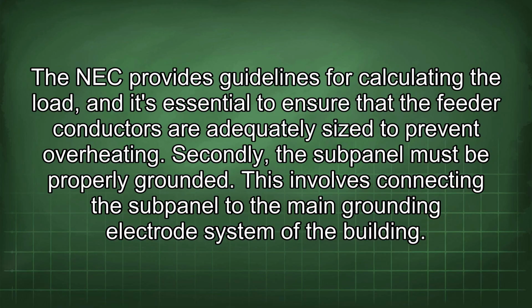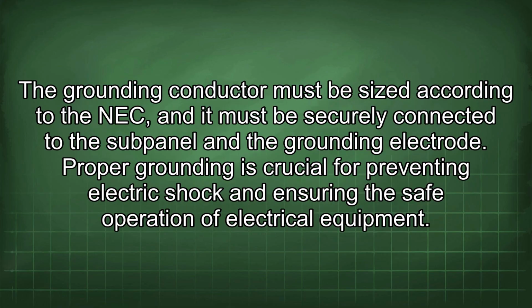Secondly, the subpanel must be properly grounded. This involves connecting the subpanel to the main grounding electrode system of the building. The grounding conductor must be sized according to the NEC, and it must be securely connected to the subpanel and the grounding electrode. Proper grounding is crucial for preventing electric shock and ensuring the safe operation of electrical equipment.